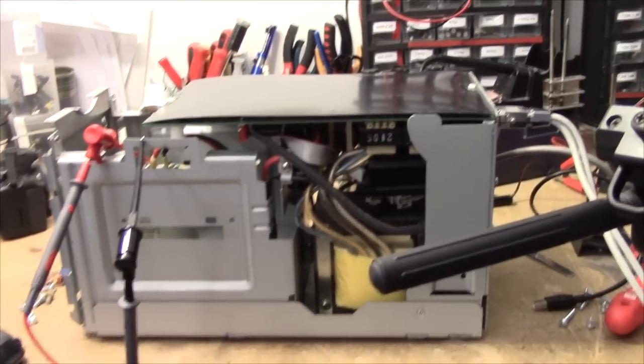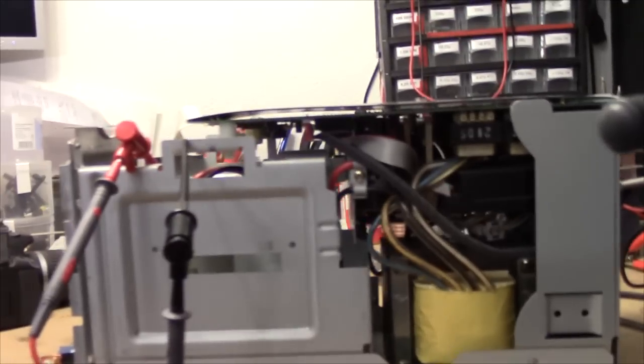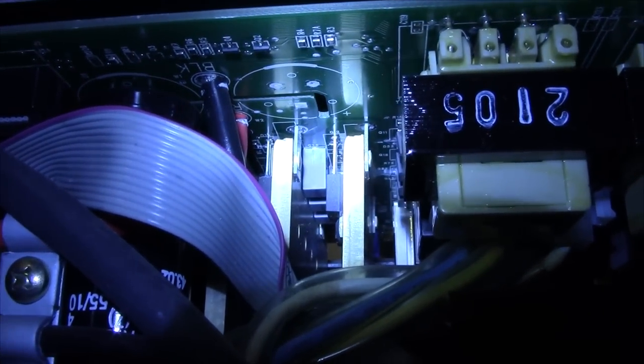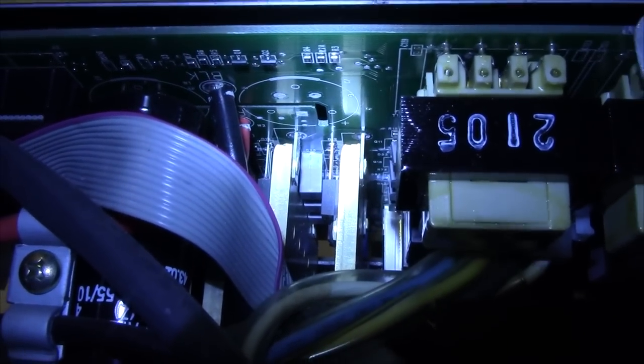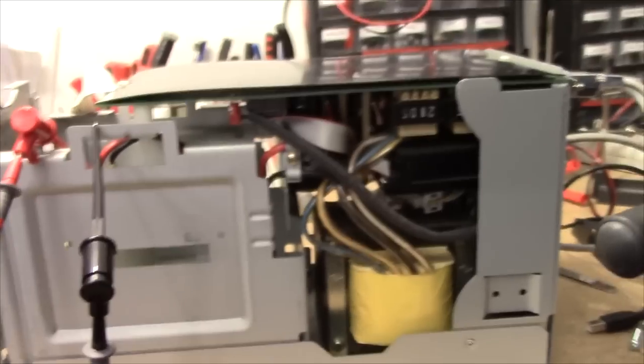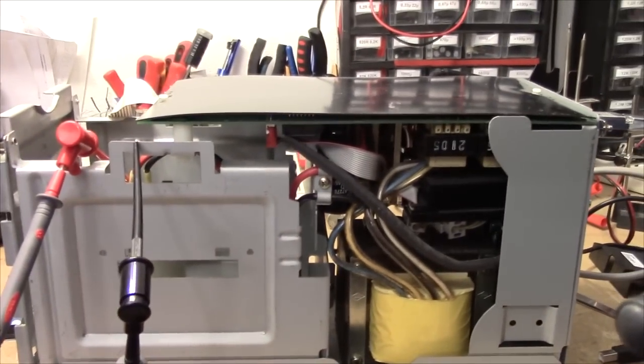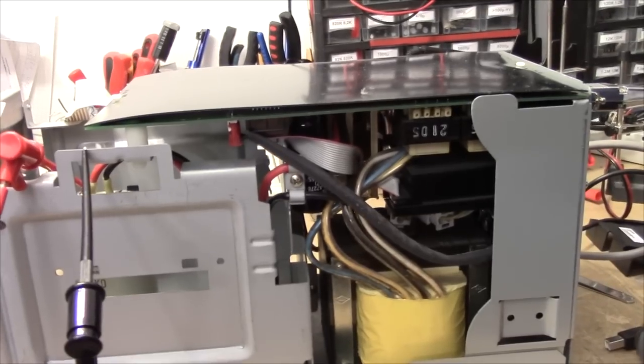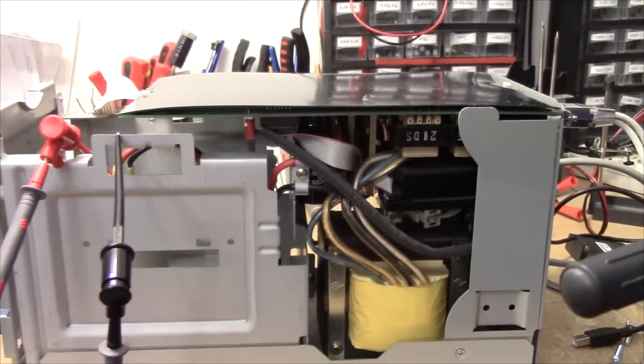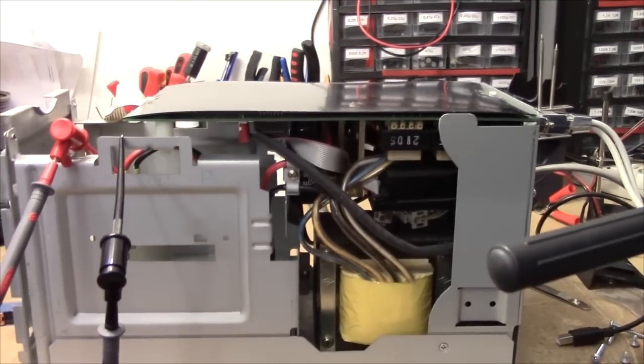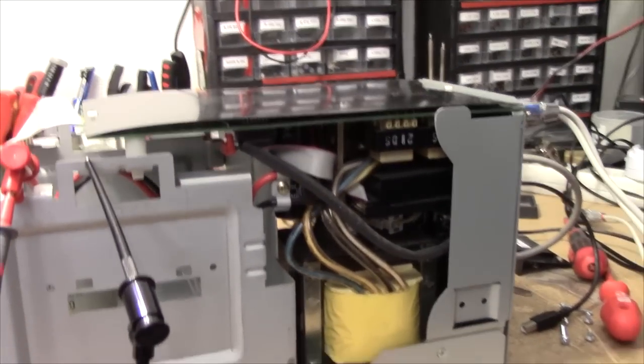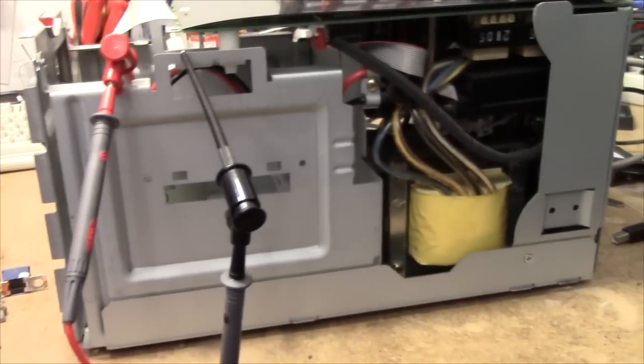Another thing with these black 1000 and 1500 VA units, you might want to check out these capacitors right there between the heat sinks. Some of them have electrolytic capacitors there, and they tend to fail. And when they do, the unit will have a hard time switching over to battery. It will make a loud groaning noise, as if it was very heavily loaded, even if it isn't. That's just because those small capacitors have failed and need to be replaced. It's no biggie. That's pretty much the only problem these units tend to run into, aside from the overcharging of batteries.